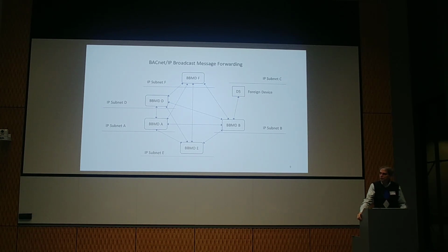Now, of course, one of the problems with BBMDs and with BACnet IP and BACnet networks in general is that as they get big, then you run into certain problems. And broadcasts are at the root of many of the problems, certainly not all of them. And we've worked with Amy and others on reducing BACnet traffic levels, especially broadcasts, as these systems get big. And you can just imagine, the more devices you have, chances are the more broadcasts that you're going to have in your system.